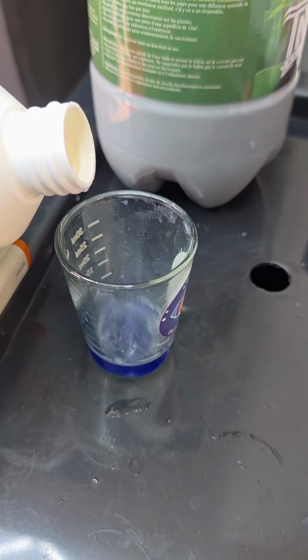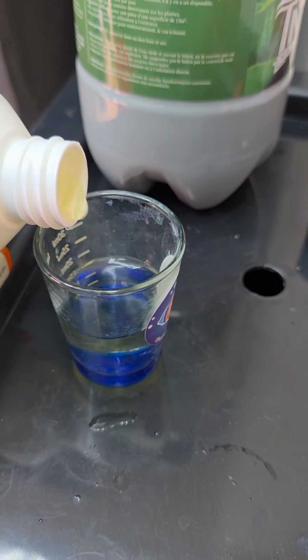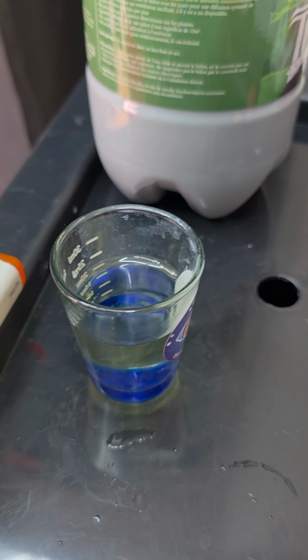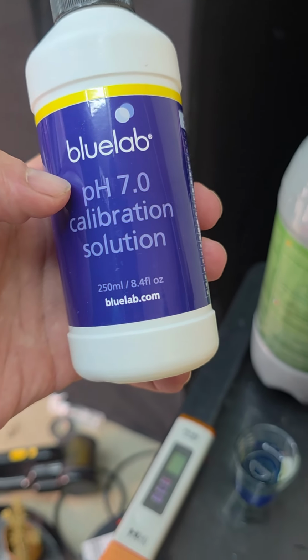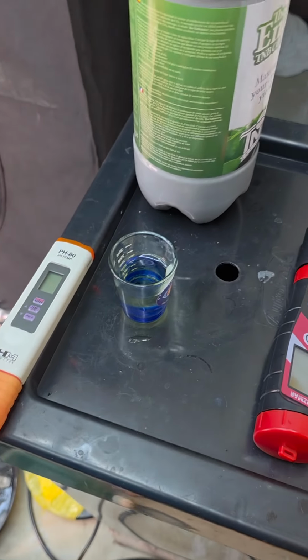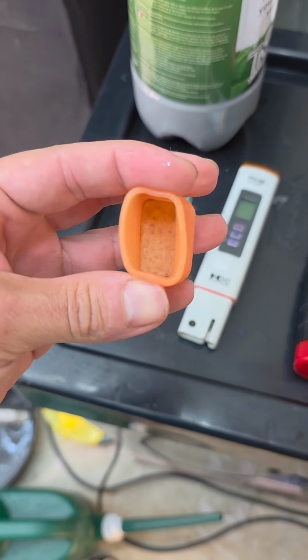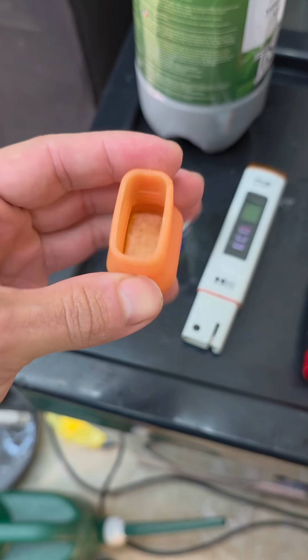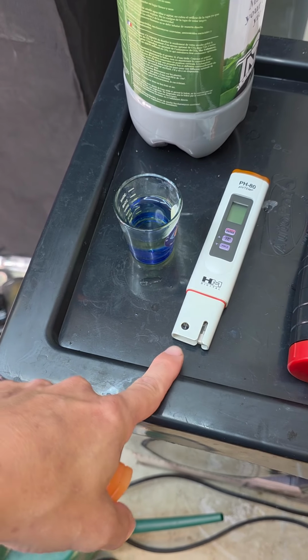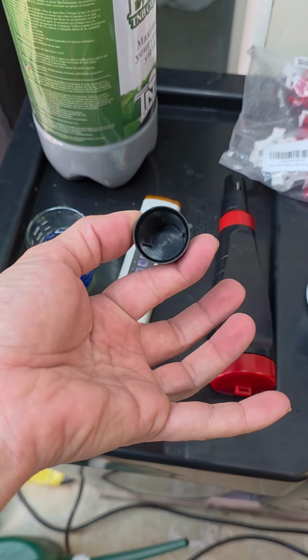Poured into this perfectly clean shot glass, measuring glass. You see this says 7.0. This is what the pH meter should read when you put it inside the solution. And you take this off of here, and you see that sponge in there. You got to keep that sponge wet to keep the probe wet. You don't want it to dry out. And there's absolutely nothing in the new one.